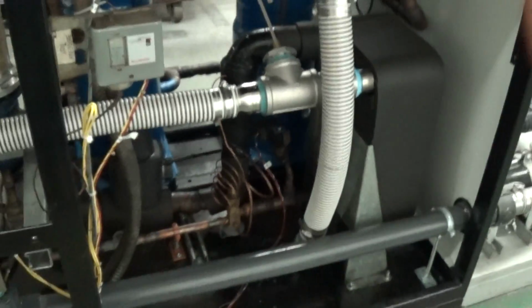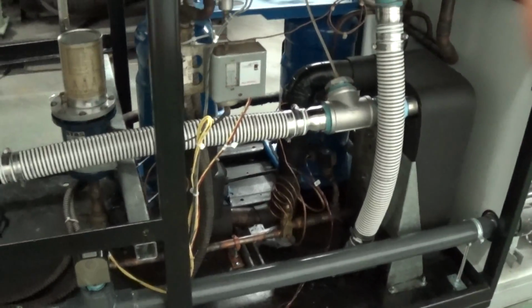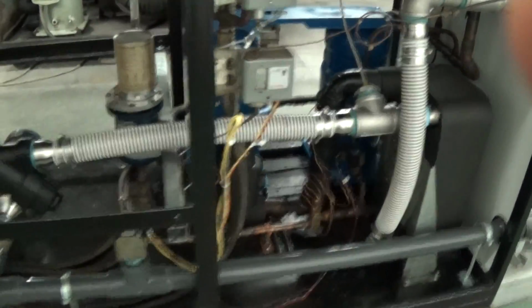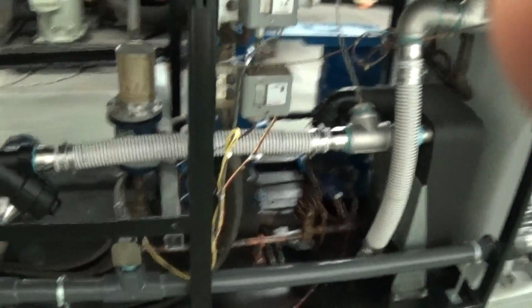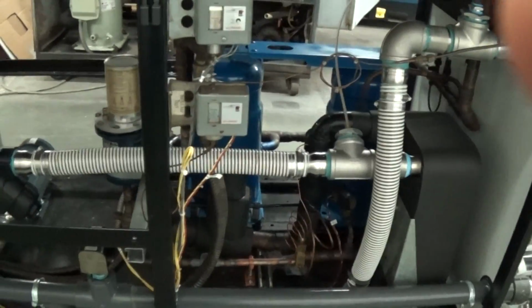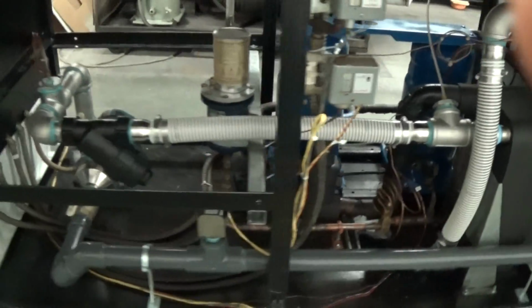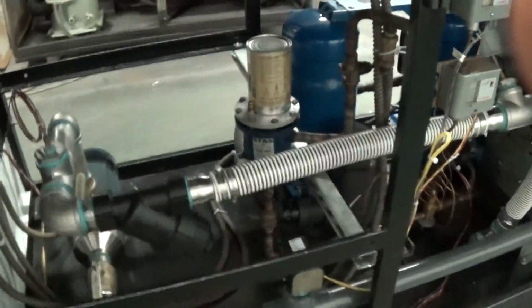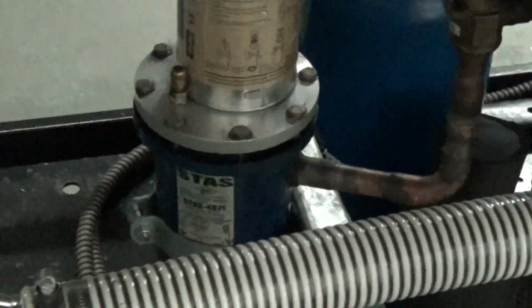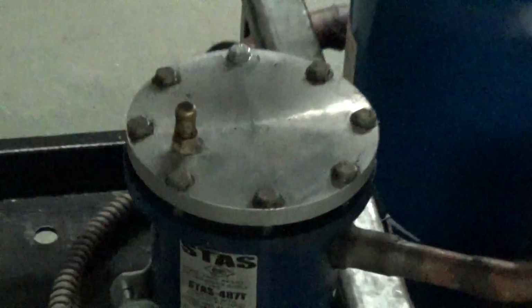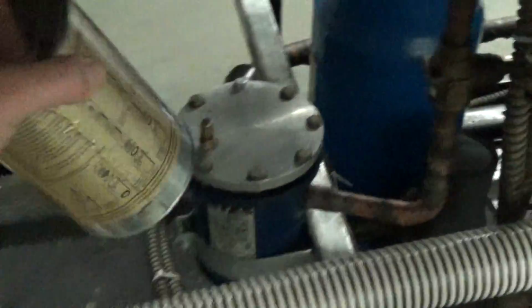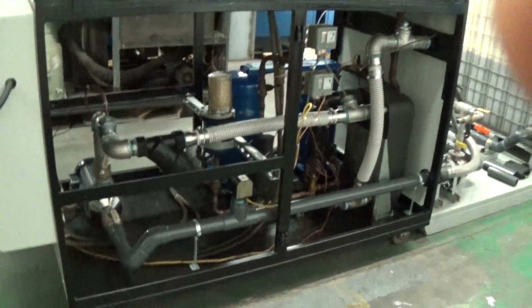We converted this machine to R407C. It's got a fresh charge of R407C and the corresponding and correct fluid or oil that's supposed to go in each compressor. After we run this for a little bit more today, we're going to put in a new core in that filter cartridge and change the oil in the compressors, as I emailed the customer. Just good practice.